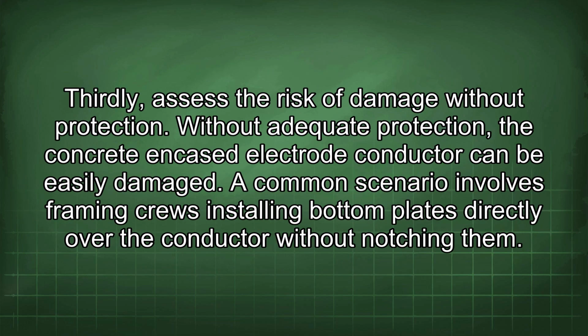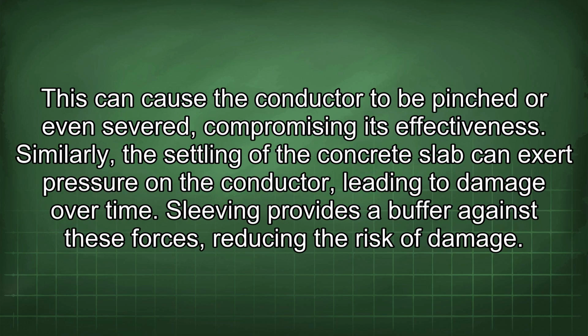Thirdly, assess the risk of damage without protection. Without adequate protection, the concrete encased electrode conductor can be easily damaged. A common scenario involves framing crews installing bottom plates directly over the conductor without notching them. This can cause the conductor to be pinched or even severed, compromising its effectiveness. Similarly, the settling of the concrete slab can exert pressure on the conductor, leading to damage over time. Sleeving provides a buffer against these forces, reducing the risk of damage.